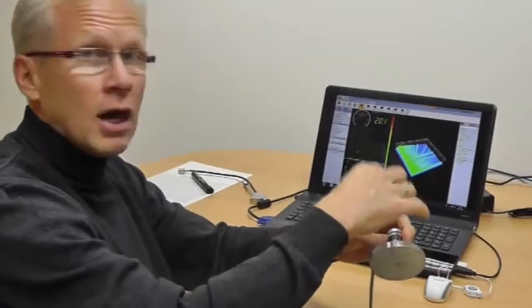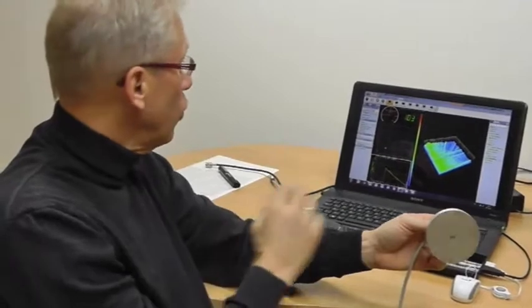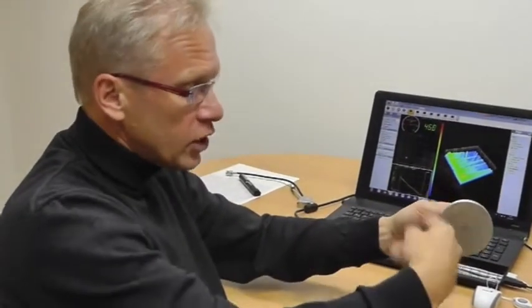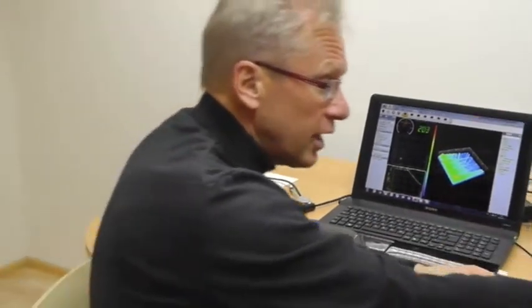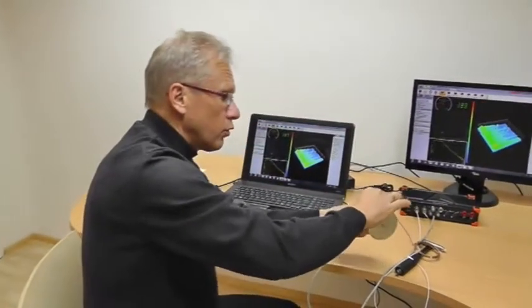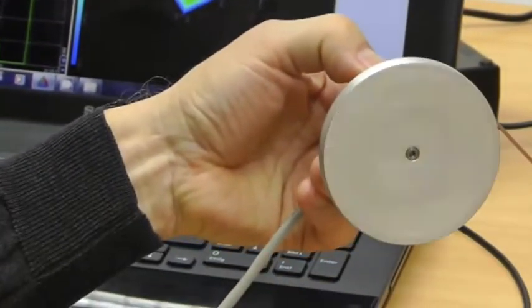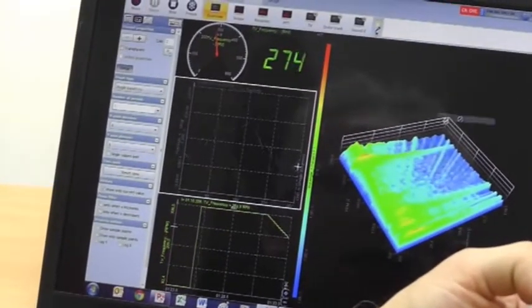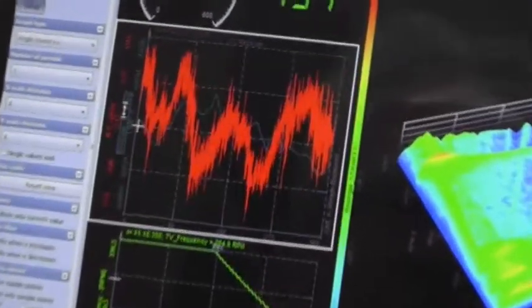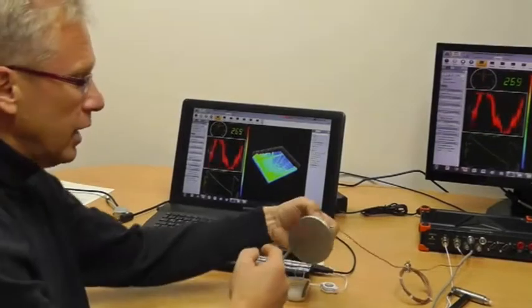Very nice measurement, precise counter measurement is necessary to show that in angle-based and time-based. So here also we see the rotation vibration. But how about the body vibration? Body vibration needs to be measured in an unbalance signal. I just take my unbalance sensor and put it on top of the shaft and make this measurement again. So here we see the angle-based measurement. And now I add on this channel, the vibration channel in here. So now we see a body vibration and a rotation vibration at one time.